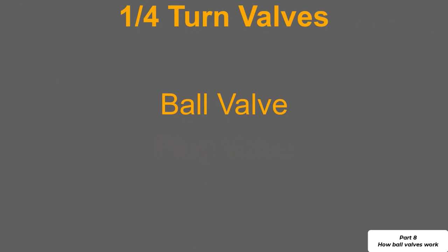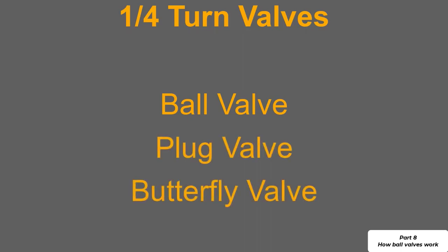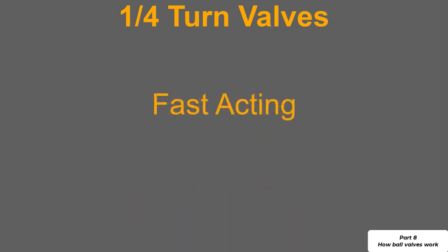Other valves at a quarter turn would include the plug valve and the butterfly valve. As with all quarter turn valves they are quite quick to operate. You can install a gearbox on the top, a planetary type gearbox, although this means you'll slow down the actuation speed of the valve or what they refer to as the response time.